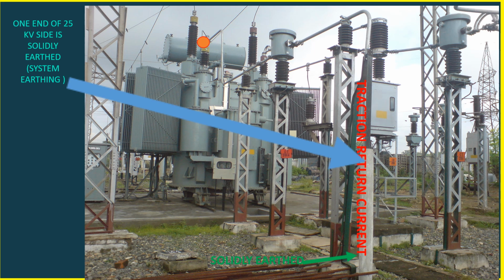but both are live. The 25 kV side has two bushings: one is given to our overhead conductors and the other bushing is solidly connected through earth. This earth is further connected to a buried rail, and from the buried rail to the railway track, to act as neutral.